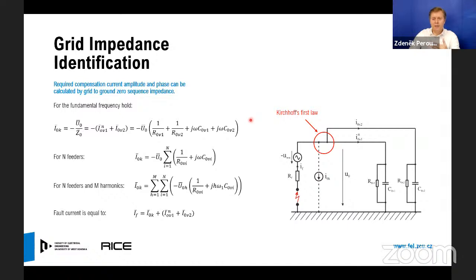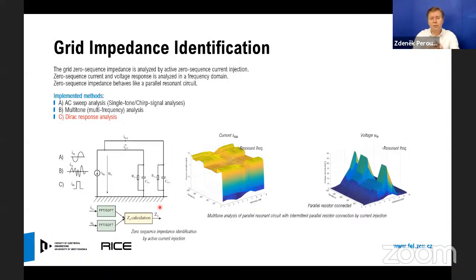The idea is very simple, but the problem is how to calculate the compensation current. The compensation current can be calculated from Kirchhoff's current law in this node. And if we have a look at the circuit configuration, the compensation current can be derived from the known or measurable zero sequence voltage and the grid impedance. So if we are able to know the grid impedance, then we are able to calculate the compensation current generally for N feeders and M harmonics. And the fault current is equal to the compensation current plus the zero sequence current of all N feeders in the system. The problem is how to identify the grid impedance. Nevertheless, we have one big benefit.